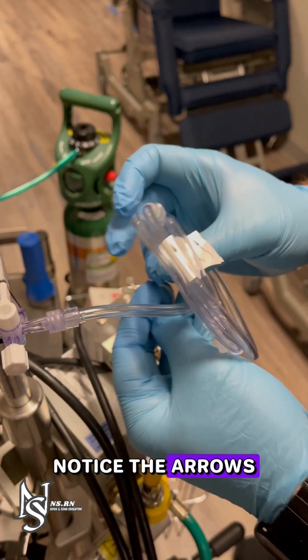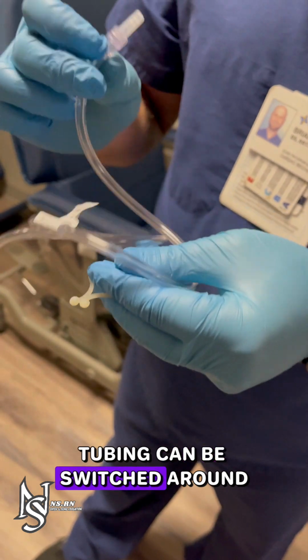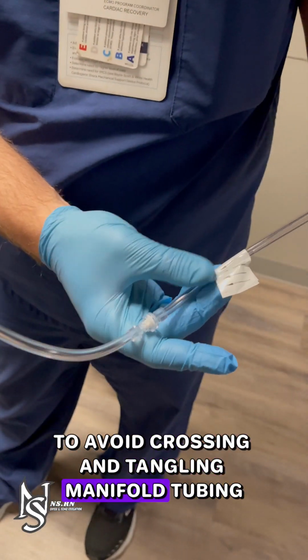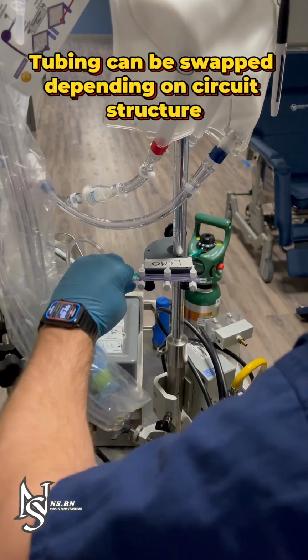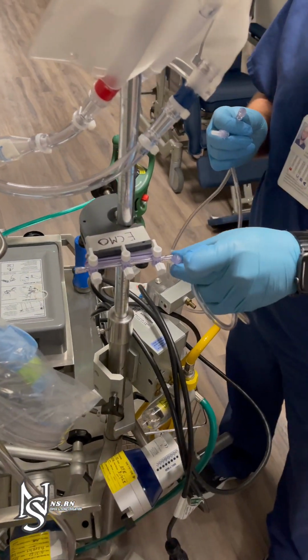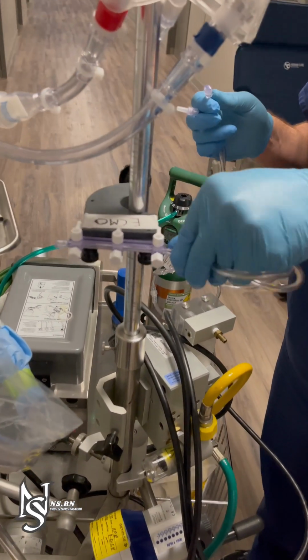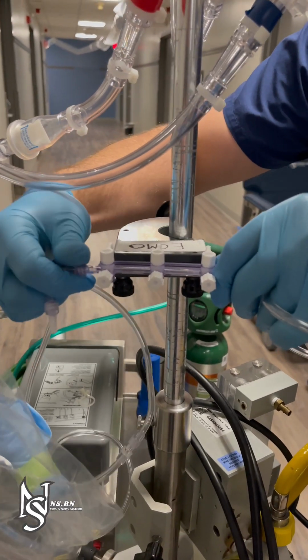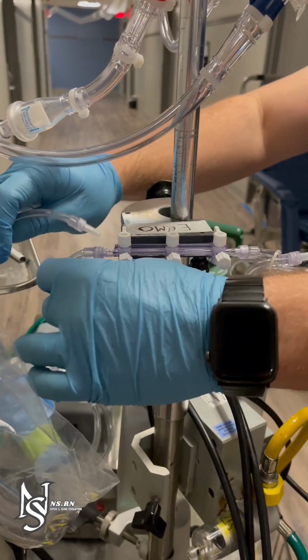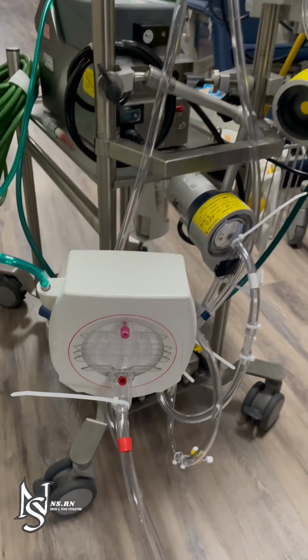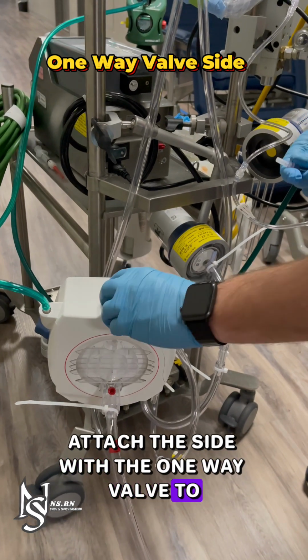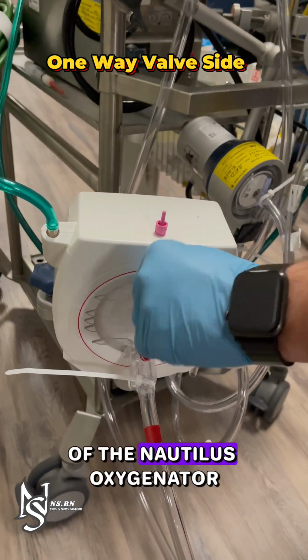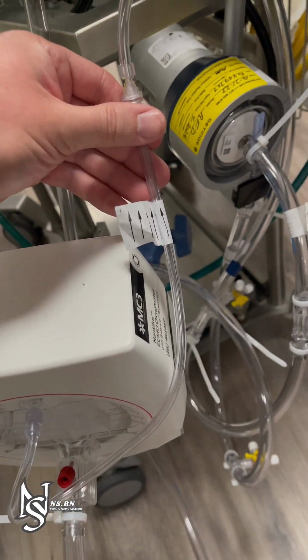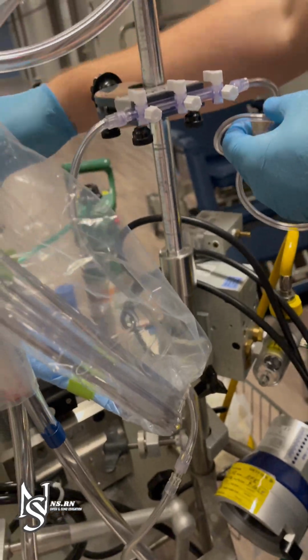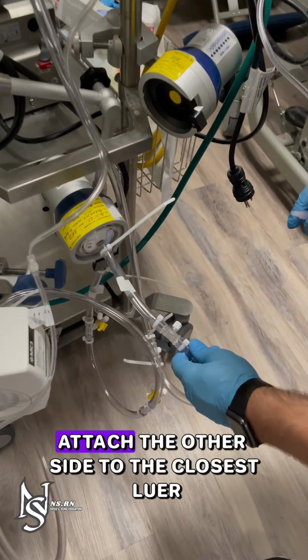Uncoiled tubing. Notice the arrows and one-way valve to show direction of flow. Tubing can be switched around depending on circuit structure to avoid crossing and tangling manifold tubing. Attach the side with the one-way valve to the top connector on the back arterial side of the Nautilus Oxygenator. Attach the other side to the closest luer lock connector on the negative side.